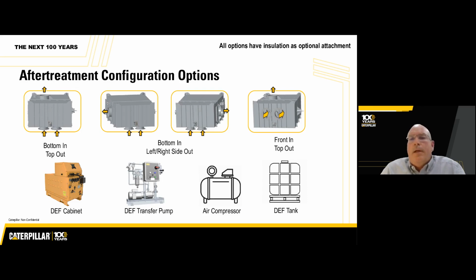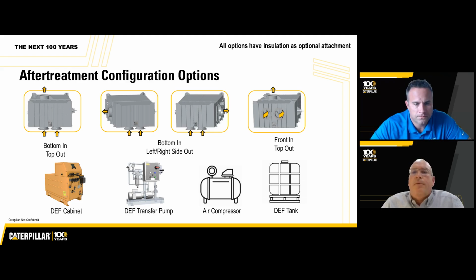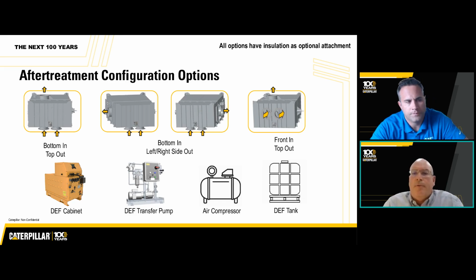Here we're showing the different aftertreatment configuration options I just mentioned. Even for a new installation, you may need a different inlet and outlet configuration based on the design of your room or enclosure. We offer a variety of different inlet and outlet configurations as part of our standard options for these systems. We also have two different types of dosing cabinets depending on the type of SCR catalyst being used - a low flow and a high flow DEF cabinet.